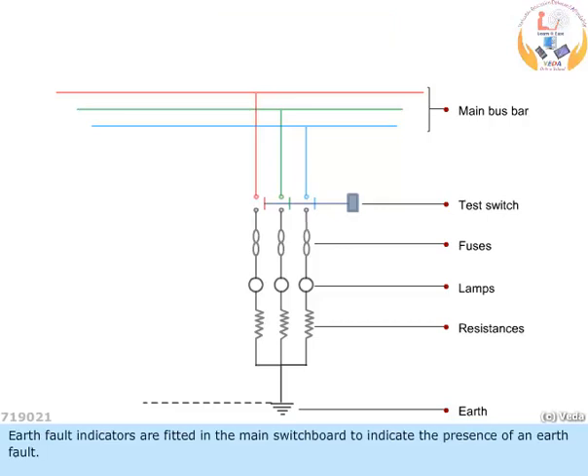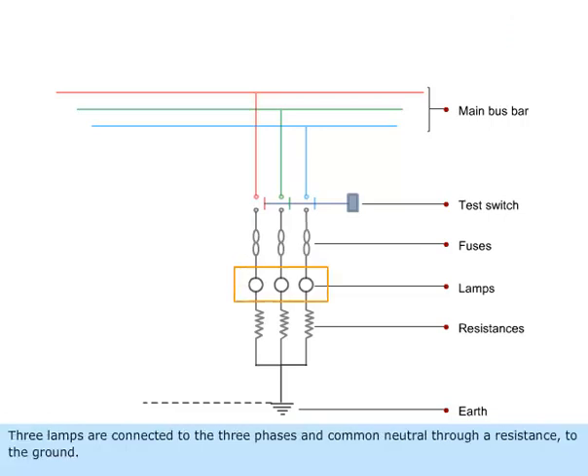Earth fault indicators are fitted in the main switchboard to indicate the presence of an earth fault. Three lamps are connected to the three phases and common neutral through a resistance to the ground.